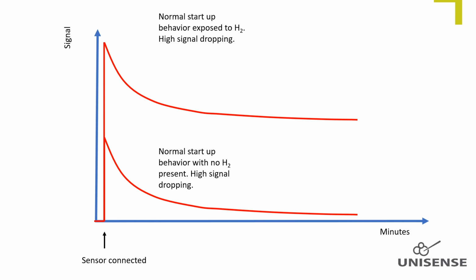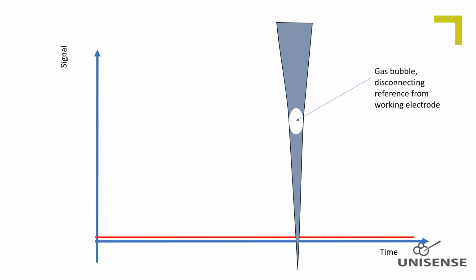If there is not such an initial peak signal, but instead the signal does not rise much from zero when connecting it to the amplifier, it might be due to a gas bubble stuck in the tip, which disconnects the working electrode from the reference. There must be a gas/air phase in the electrolyte cavity in order to make room for temperature-induced expansion of the electrolyte. And if the sensor package is turned upside down during shipment, a gas bubble can be trapped in the tip. Such an air bubble can be removed by shaking the sensor like demonstrated here. The bubble will become loose and rise to the top of the electrolyte cavity, and connection will be restored.